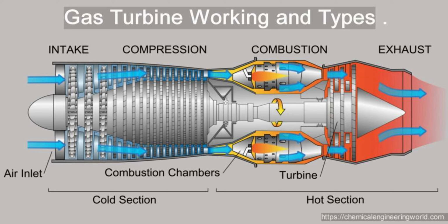Who is authorized to repair a fuel flow indicating system? The components can be repaired only by an FAA approved repair station certificated for particular instruments. Where can you find the electrical power requirements for a fuel flow indicating system? In the aircraft maintenance manual. Where in the fuel system is the fuel flow transmitter located? Between the fuel control and the fuel nozzles.